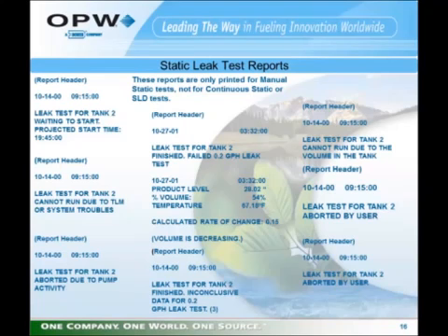If you look at them, you could see that starting at the left and moving by columns over to the right, that first printout is where you have programmed for a tank to start testing right now, but for some reason the device has determined that the conditions aren't yet right to begin testing that tank, and it will give you a projected start time.